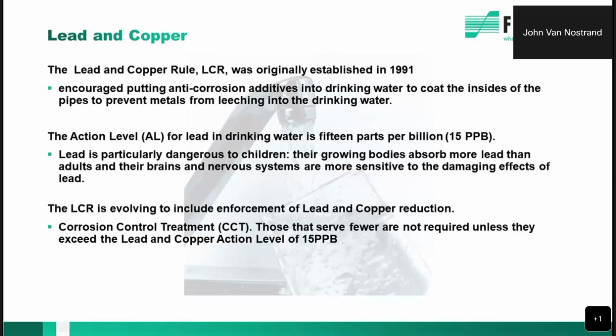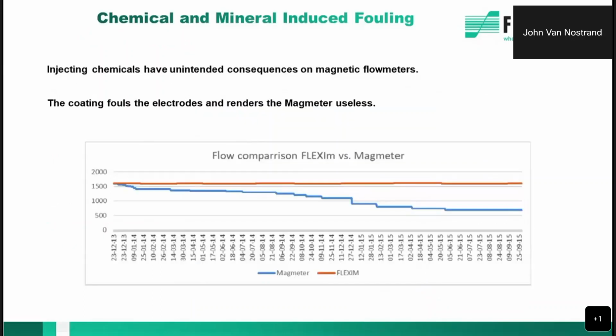And then what happens is, you'll wind up injecting orthophosphate into the water, and injecting chemicals has unintended consequences on magmeters. The coating fouls the electrodes and basically renders the magmeter useless. So what we're seeing here is a study that we had done at a well over a period of time, this is nearly 2 years, where the FLEXIM meter was installed right next to a leading manufacturer of magnetic flow meters. And over time, in this case, manganese coated the inside of the pipe. Orthophosphate and manganese have the exact same effect on magnetic flow meters. One actually coats the electrodes so that the electrode signal cannot be detected and they can't feel the water, essentially, while the other one creates a direct short. But the end result is they start out reading properly, and over time they read lower and lower until they just fail.